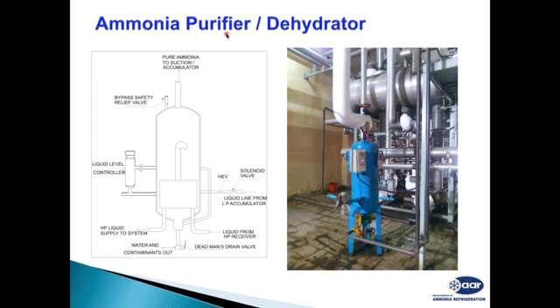This is an ammonia dehydrator or ammonia purifier. The function of this unit is to remove the water. What has been done here is that it is provided a high pressure liquid from the receiver and going back to the system. They're taking the samples from the low pressure side receiver. You can show here the actual installation. Sample is taken from the low pressure side. So if ammonia comes into the system, it will evaporate, become gas, and go back to the system.